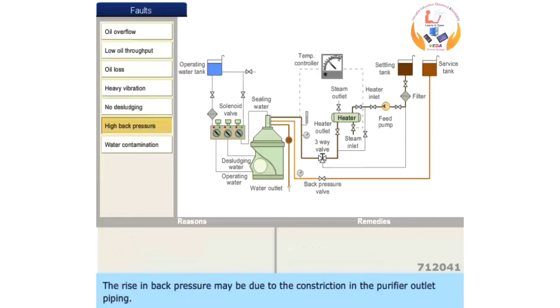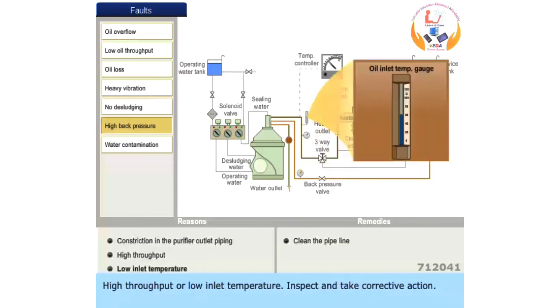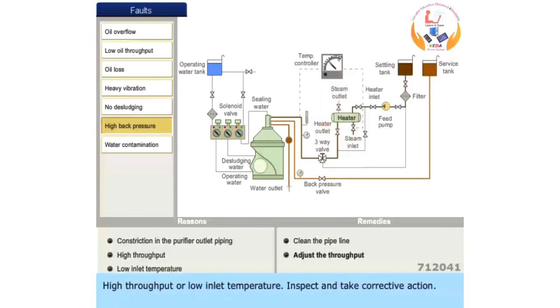The rise in back pressure may be due to constriction in the purifier outlet piping, high throughput, or low inlet temperature. Inspect and take corrective action.